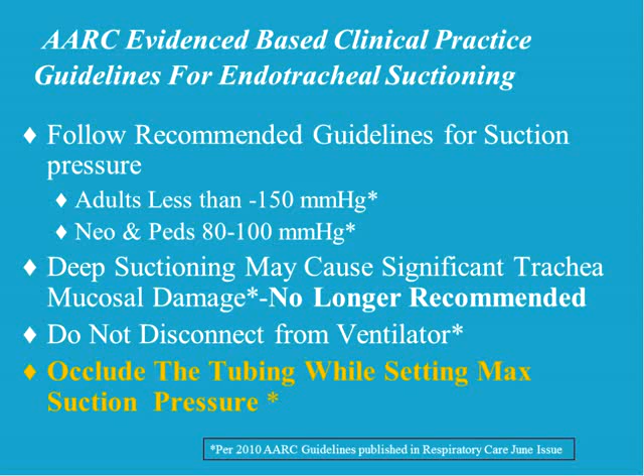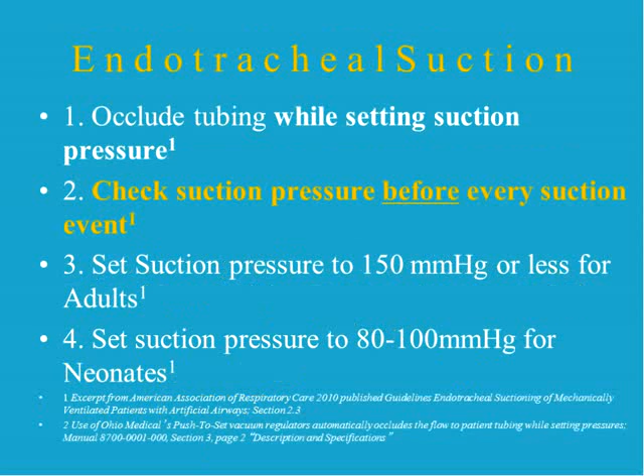So rather than setting the suction regulator like a flow meter, you have to occlude it to set it. Again, occlude the tubing while setting the suction pressure, and also check the suction pressure before every suction event. When you go to do the endotracheal tube procedure, you should occlude the tubing to make sure the pressure is where you expect it to be. Oftentimes in clinical audits, we see this pressure being way higher than wanted, because someone used the same catheter to suction the nose or the mouth and didn't return the pressure back to normal before doing a suction event. So set that pressure to 150 or less, again using the minimal pressure appropriate to achieve your goal, and set the suction pressure to 80 to 100 for neonates and peds.